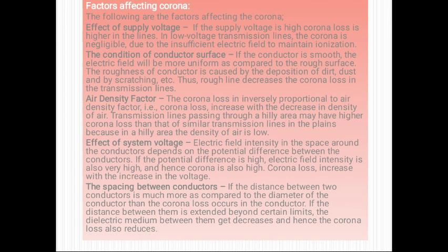Next is effect of system voltage. Electric field intensity in the space around the conductor depends on the potential difference between the conductors. If the potential difference is high, electric field intensity is also very high, and hence corona is also high. It means as the system voltage increases, corona loss also increases. Corona loss increases with the increase in voltage.